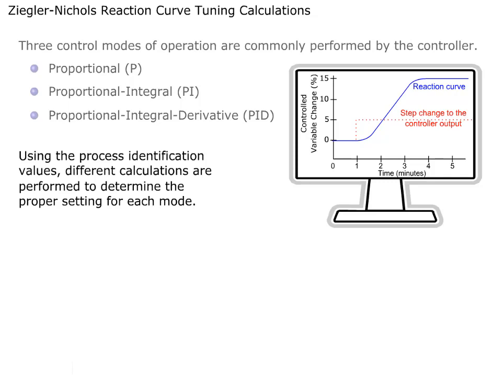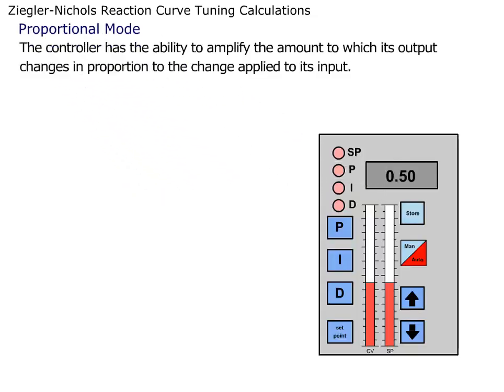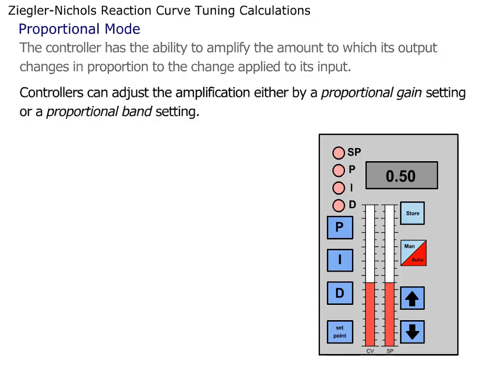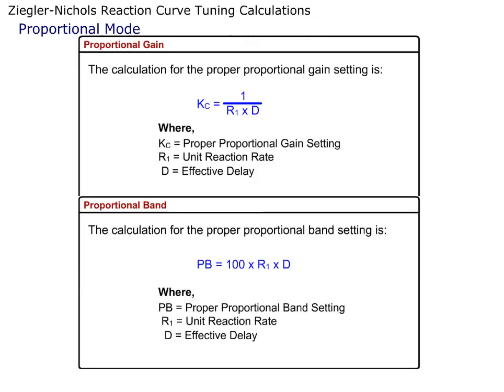Using the Process Identification values, different calculations are performed to determine the proper setting for each mode. The controller has the ability to amplify the amount to which its output changes in proportion to the change applied to its input. Controllers can adjust the amplification either by a Proportional Gain setting or a Proportional Band setting. The Proportional Gain and Proportional Band formulas are shown here.